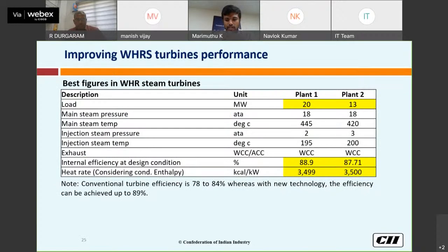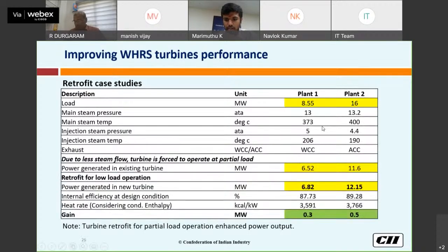So this is based on the study, some of the best figures: the heat rate and internal efficiency of the turbine. Conventional turbine is around 78 to 84. With the new technology, turbines are available with an internal efficiency of 89 and 88. Heat rate is also around 3,500 kilocalorie. And this is one case study based on retrofitting.